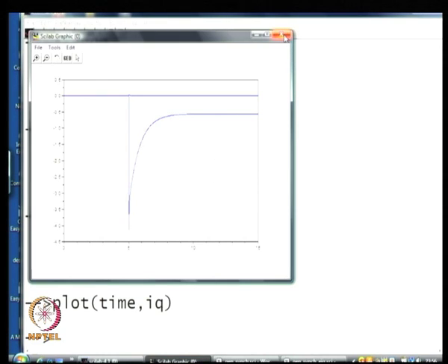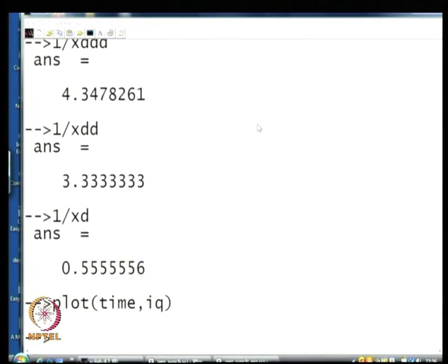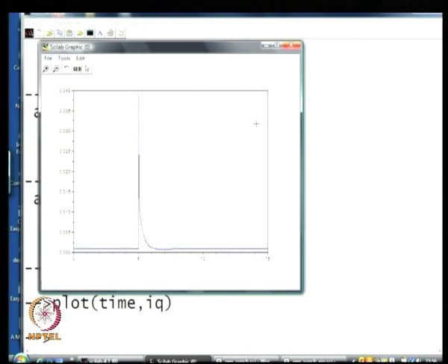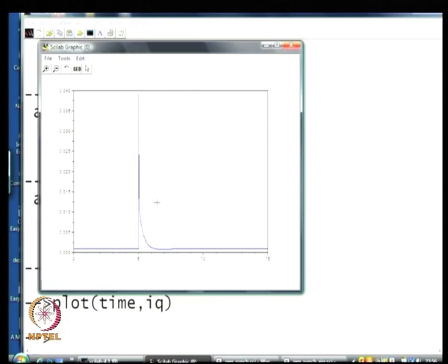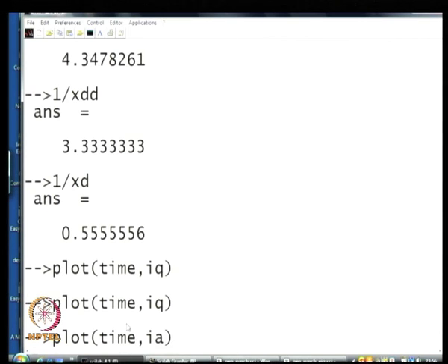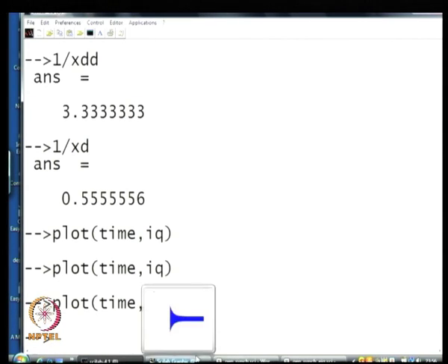Looking at i_q with stator transients neglected — it is a very small current, practically 0 at 0.04, so i_q is practically 0, and here too you do not see any oscillatory band because we have neglected the stator transients. Interestingly, i_a looks like a symmetrical 50 Hz waveform — under short circuit conditions and neglecting the stator transients, you get what looks like a symmetrical 50 Hz waveform with no DC offset.